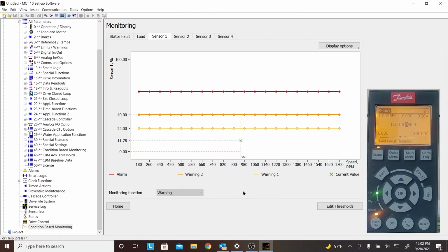And as we run this drive, we see it come up in speed. We're green, we're good, we're well below. Everything's good, no warnings on the keypad. We're at speed. Now we're in manual mode on the keypad, so you see the manual mode down at the bottom here with the triangle at 1000 RPM. Now, as we have an issue and the machine degrades and we get over the first level, keep an eye on that keypad, now we get a fault.